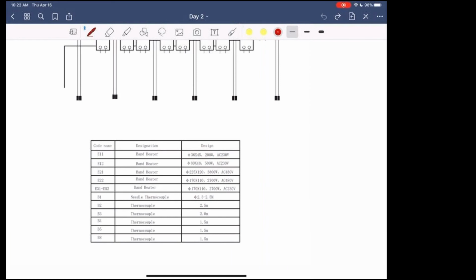The reason why they use K thermocouples is because they're more accurate than the J thermocouples, and they have a higher tolerance for heat. So you can actually have a lot more heat. You're not as restricted as you are with the J thermocouples.